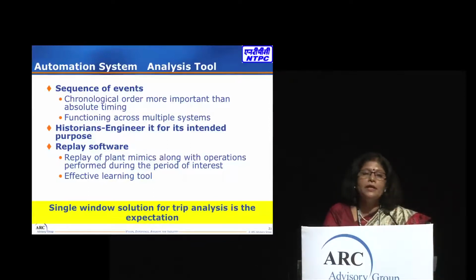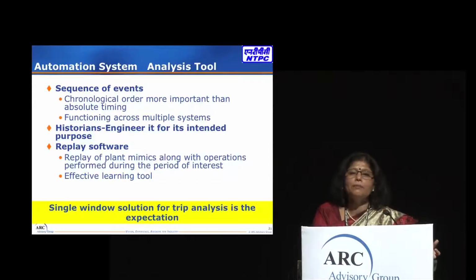For sequence of events, we have to remember that absolute timing is not important; whatever is taking place has to be chronologically correct. Similarly, for the historian, just dumping data is not enough. It has to be engineered in such a way that it meets the intended purpose. As an end user, my requirement is that all this analysis, whether SOE or historian, should be available on a single window.